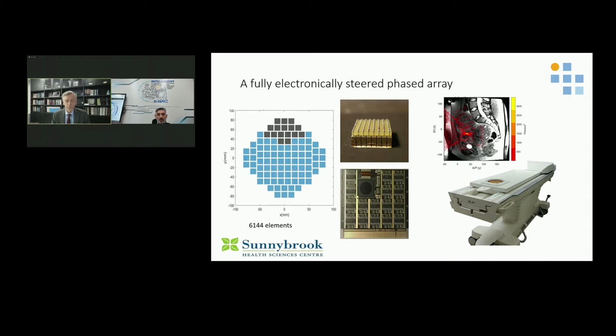And if you look on the MR image there of a fibroid, there you see the treatment planning, where the planning is showing where the acoustic focus is. Since you can control each of the elements and blocks, you can turn them on or off, the field shape is changed and can be completely controlled. So you can generate multiple focal spots, and you can steer the beam with electronic beam steering really fast. And you also can cause nulling of the field, so you can eliminate the acoustic pressure in locations while still having focusing.